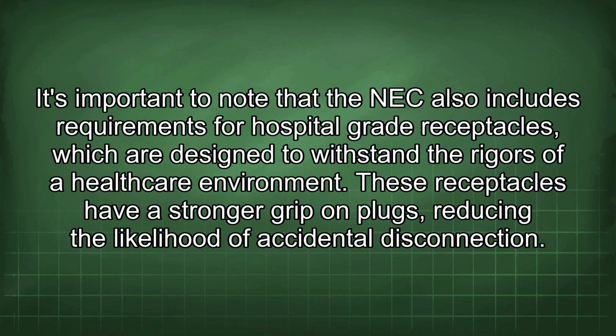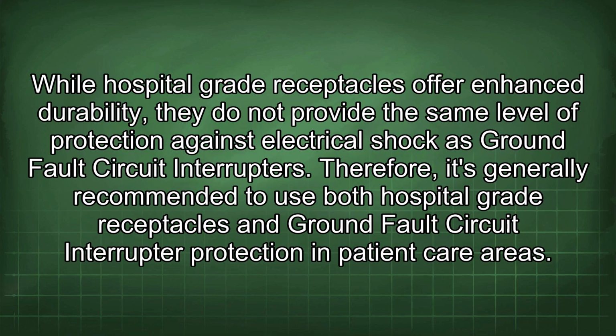It's important to note that the NEC also includes requirements for hospital-grade receptacles, which are designed to withstand the rigors of a healthcare environment. These receptacles have a stronger grip on plugs, reducing the likelihood of accidental disconnection. While hospital-grade receptacles offer enhanced durability, they do not provide the same level of protection against electrical shock as ground fault circuit interrupters. Therefore, it's generally recommended to use both hospital-grade receptacles and ground fault circuit interrupter protection in patient care areas.